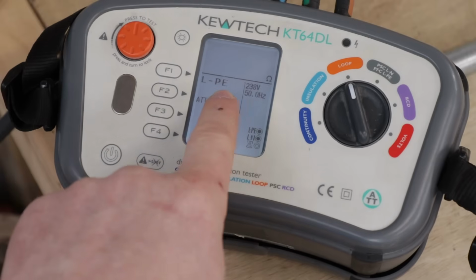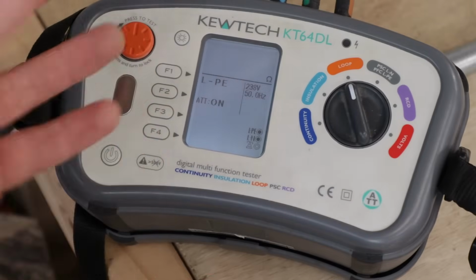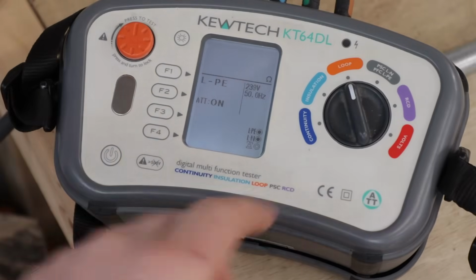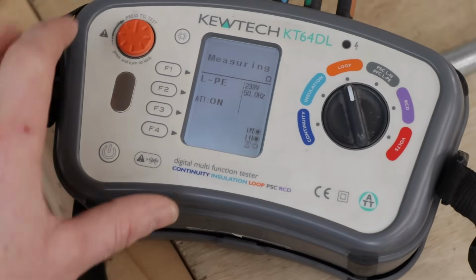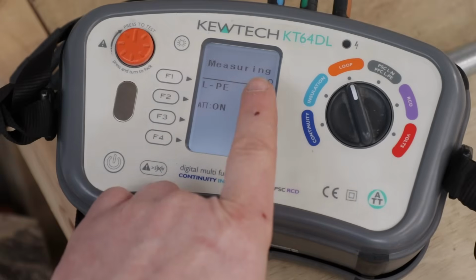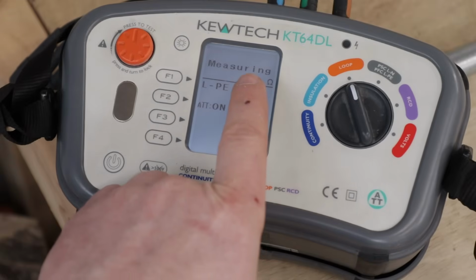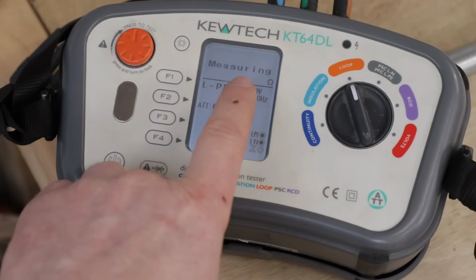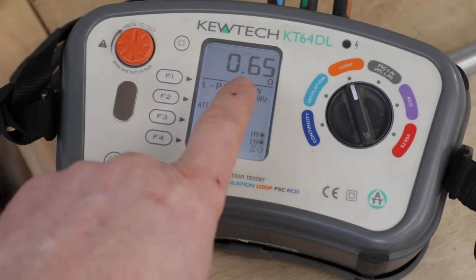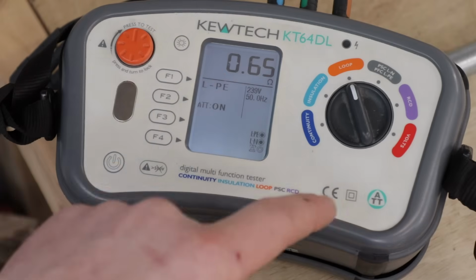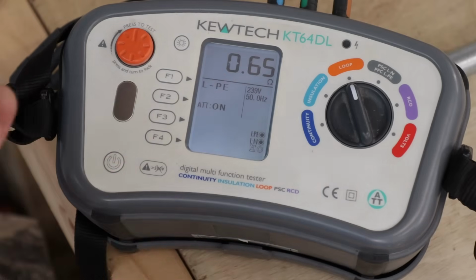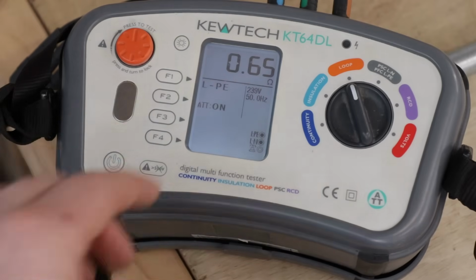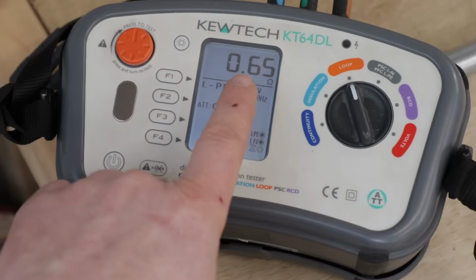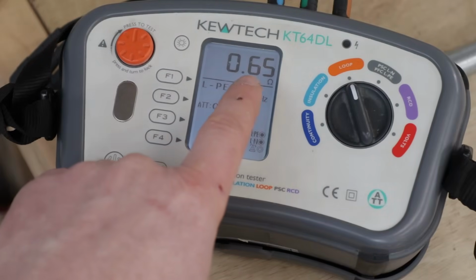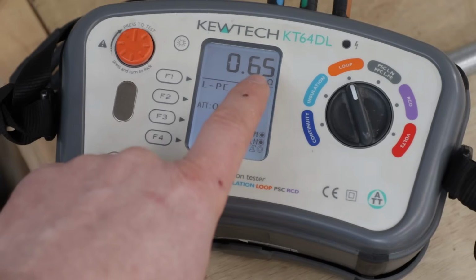So if I shorted out the live and earth, I need to know that I'm going to get that fault current to flow to trip out my breaker. So if I hit the test button there now, it'll measure the total impedance of this circuit. Now we call it impedance, we don't call it resistance, because there's no such thing as a purely resistive circuit. There's also capacitive reactance and inductance. It's the total amount of things that are impeding current flow. So we can just take it as resistance just for this video. So 0.65, that's pretty small, so that's pretty good. That's the total resistance of that circuit all the way out to the transformer.